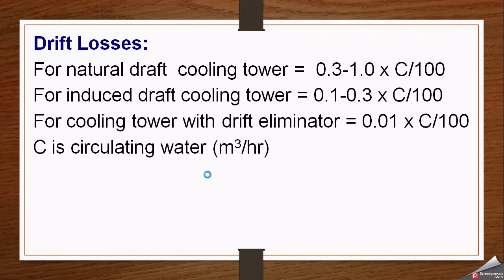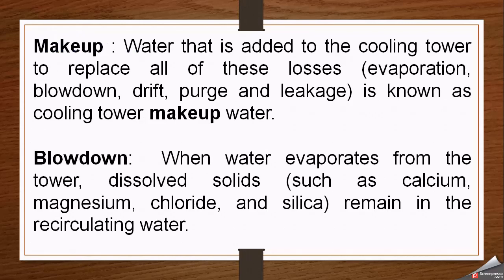In all these relations, C is the circulating water circulation rate taken in cubic meters per hour. Another important term in cooling tower operation is makeup water — the water that is added to the cooling tower to replace all losses including evaporation, blowdown, drift, purge, and leakage. All types of losses are covered by adding fresh water, known as makeup water.